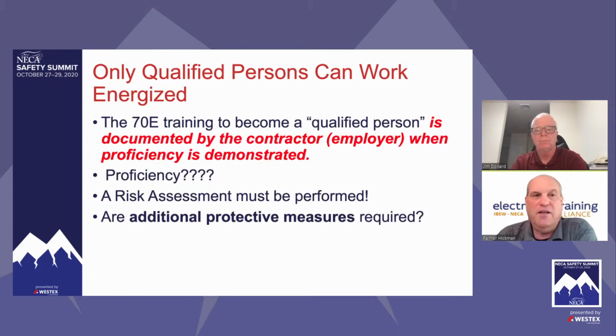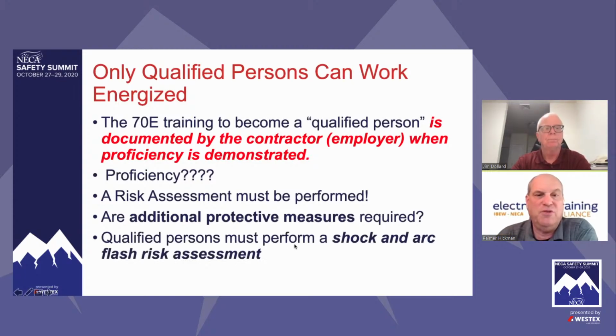So, and even the permit that we talked about earlier, the energized electrical work permit, where it has exceptions for things like voltage testing, but it's not an exception from doing a risk assessment, a shock and arc flash risk assessment. You still need to do that, and you still need to wear PPE. So it's not an exception from PPE. It's not an exception from your risk assessment. Even for the most common, allowable, and necessary justified energized work, verifying absence of voltage during lockout, tagout. You need PPE. You need to do a shock and arc flash risk assessment. Yeah, and when we consider those additional protective measures, the first thing that we have to consider is creating an electrically safe work condition.